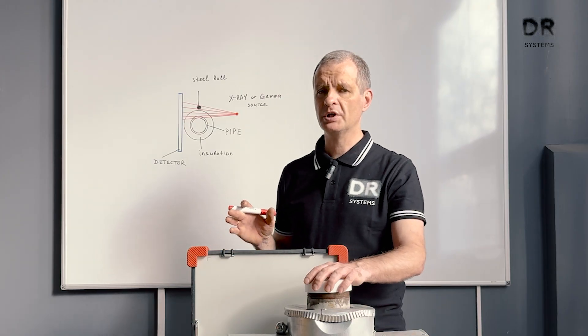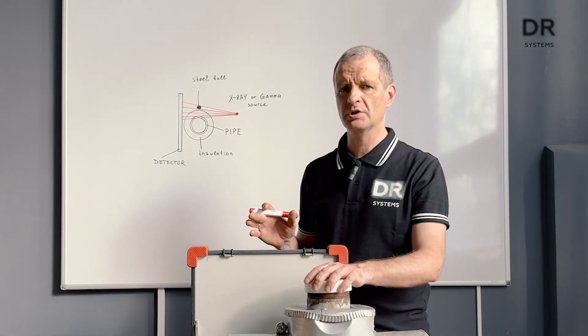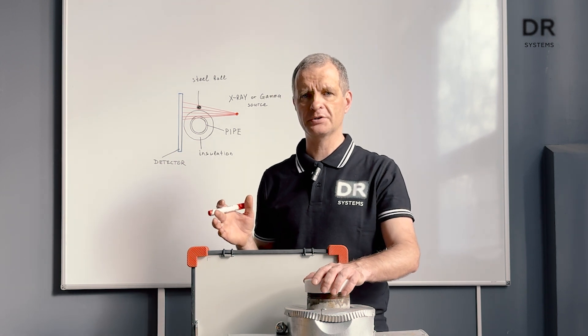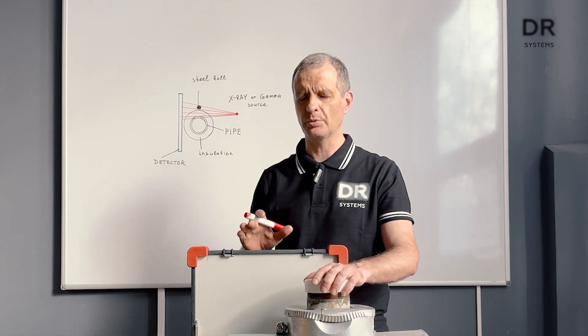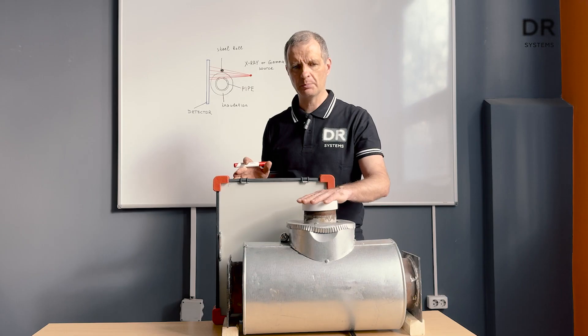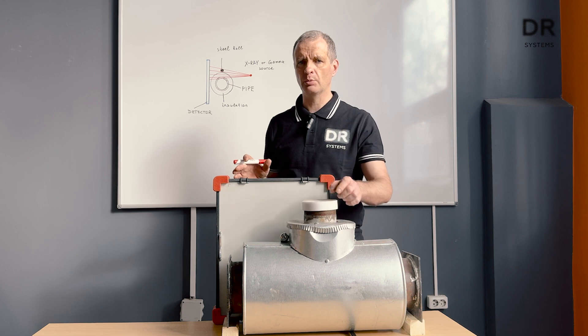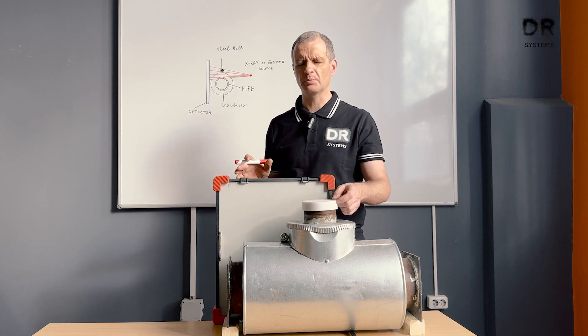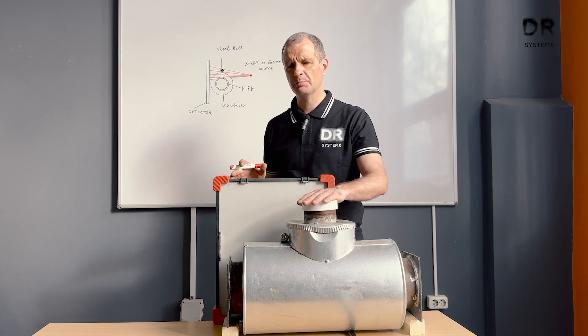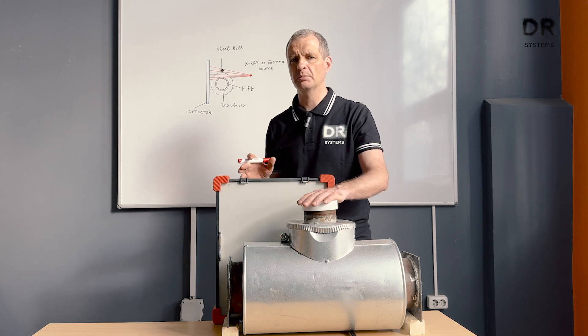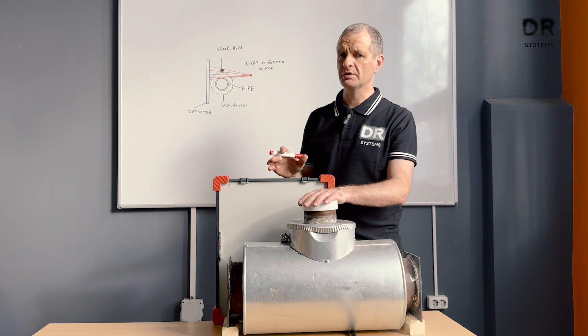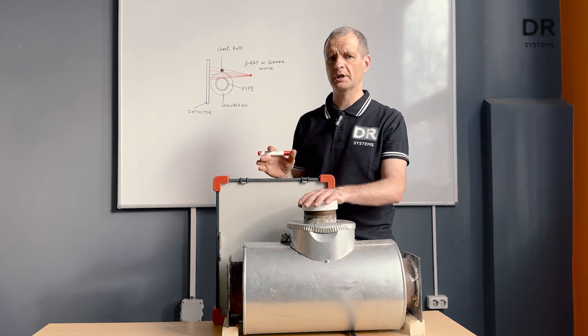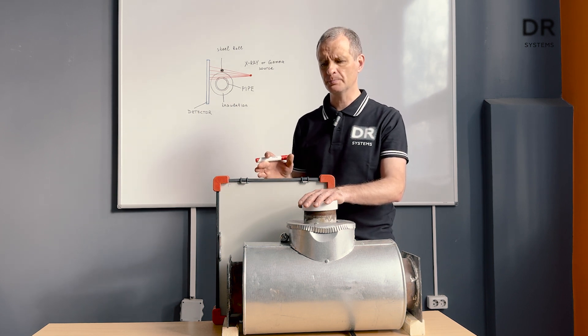Then we have to choose a really strong x-ray source to do this. This pipe is only 4 inch and the wall thickness is 4 millimeters, and this pipe can be measured by 300 kV source or iridium 192.